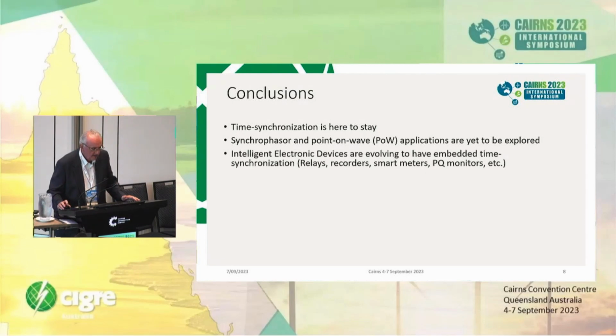Then we have embedded devices, meaning everything these days that you can talk about, from smart meters to recorders to embedded controllers on the circuit breakers. Anything like that people are thinking about, they're already doing time synchronization of the samples that are taken there. So what we're going to see is not PMUs. We're going to see a bunch of these devices across transmission, distribution, microgrids that inherently inside have capability of time synchronized sample collection and calculation of the quantities that you may wish to calculate.